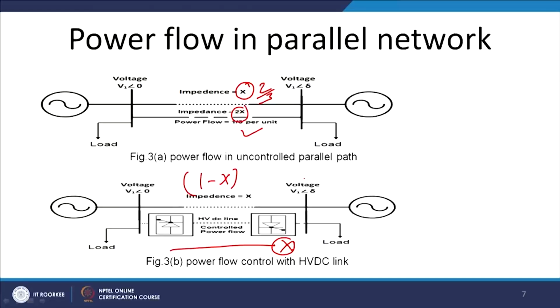This HVDC link is controllable, thus it can take x amount of power and 1 minus x amount of power will flow to the uncontrolled line. Since x is controllable, 1 minus x is controllable, and we have to maintain the power flow of this line, which is governed by its operating point, thermal limit, dielectric limit and steady state limit.